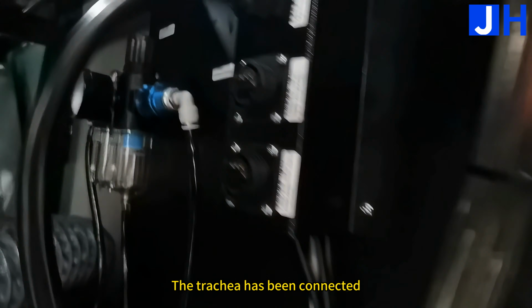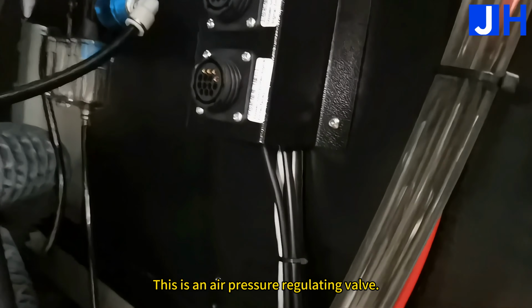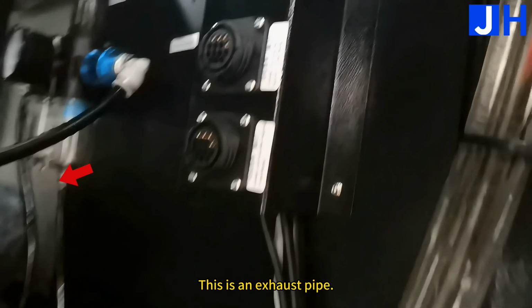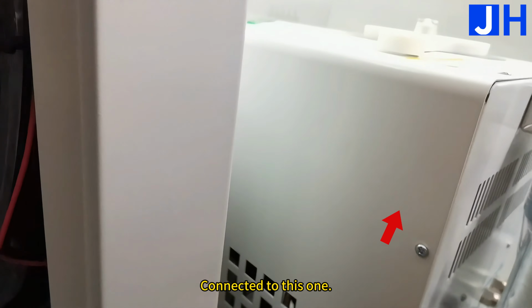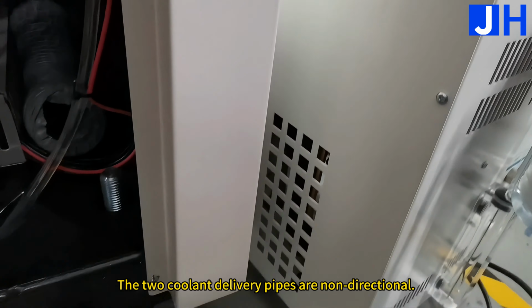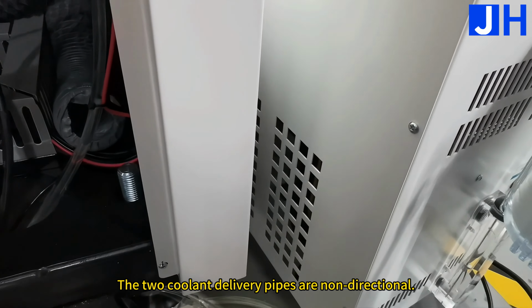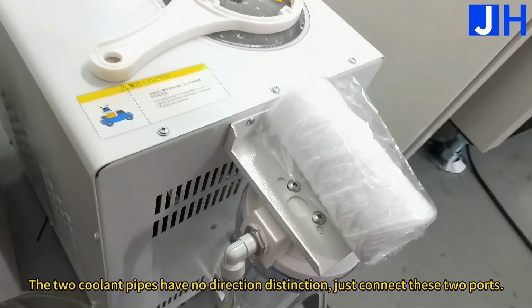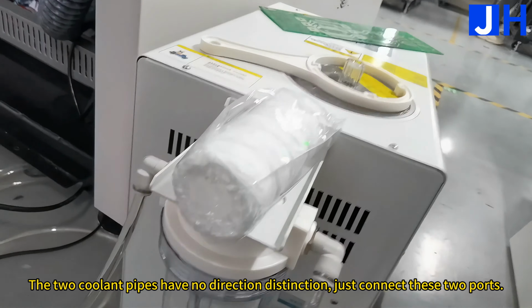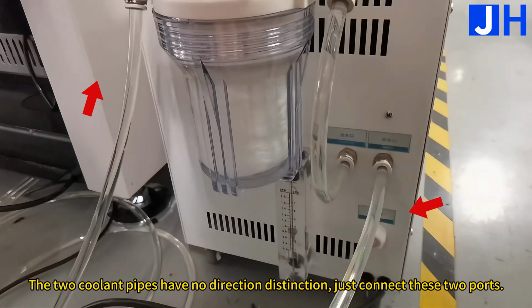This is the tracheal connector of the machine. The trachea has been connected. This is an air pressure regulating valve. This is an exhaust pipe. This is a water pipe that cools the laser, connected to this one. The two coolant delivery pipes are non-directional. They have no direction distinction, just connect these two ports.